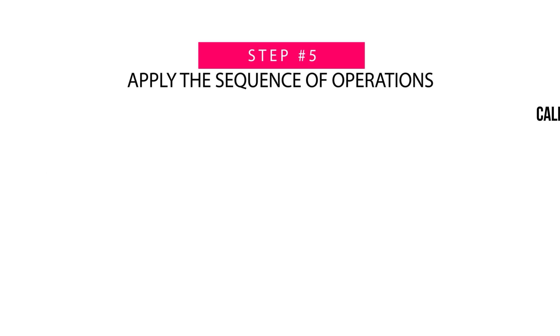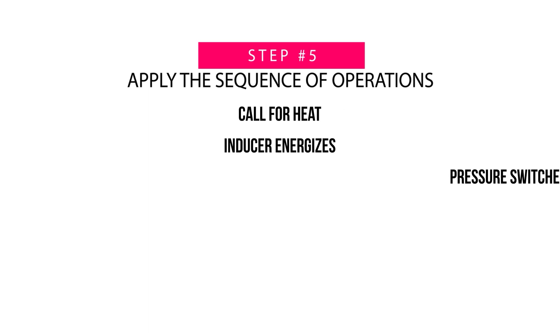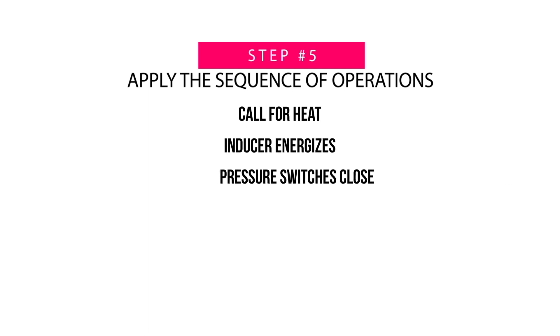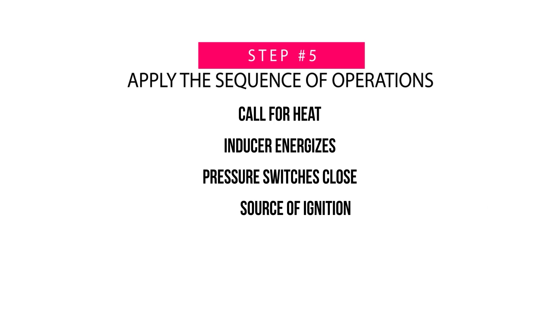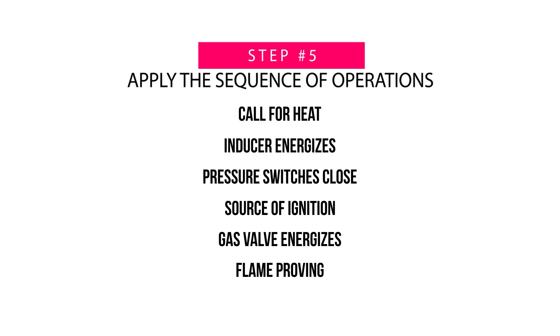A call for heat. The inducer energizes. Pressure switches close. Source of ignition. Gas valve energizes. Flame proving. And finally, the blower motor.